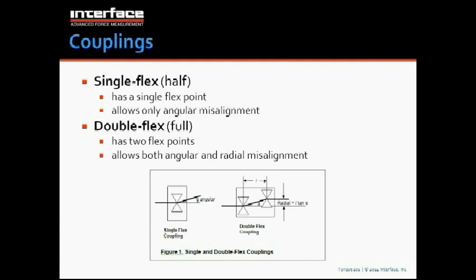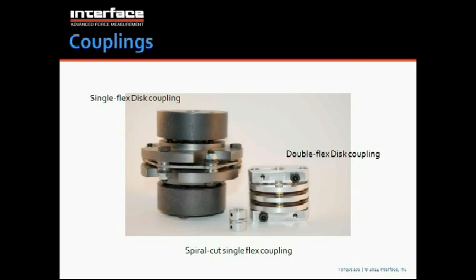And if not, if you bolt everything rigidly together, it induces bending and very serious loading into the bearings as the system spins. These are some examples of couplings. This is a disc type, and these are the kind that we recommend for torque measurement. They're very rigid torsionally and very soft in the angular deflection direction. You can see on the left there's a single flex, and in the center here is the actual flex pack or disc pack, and that's the flex, and the rest of it is quite stiff.